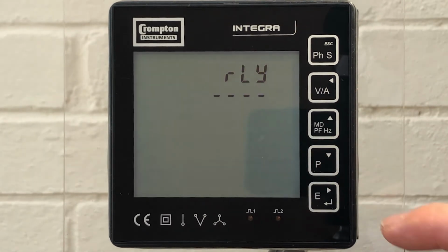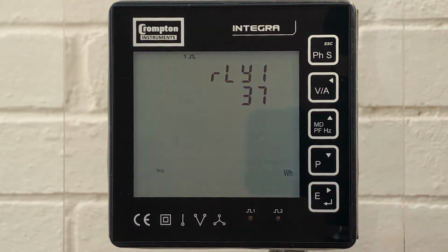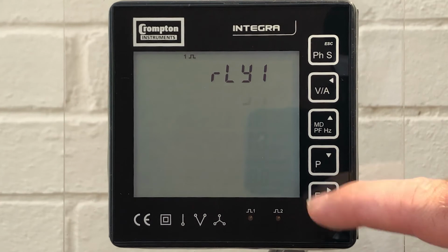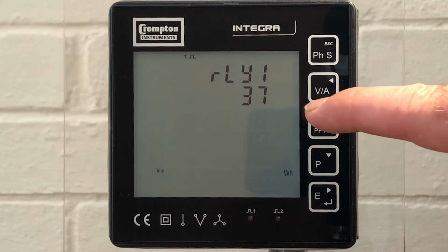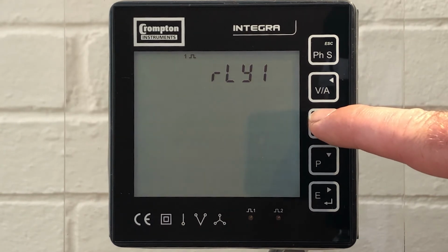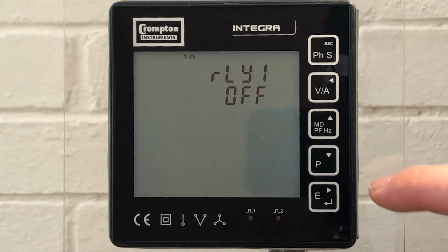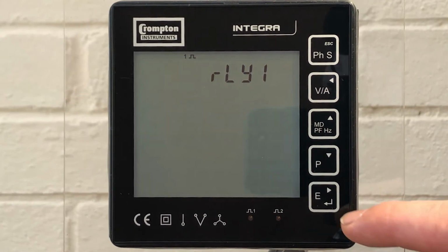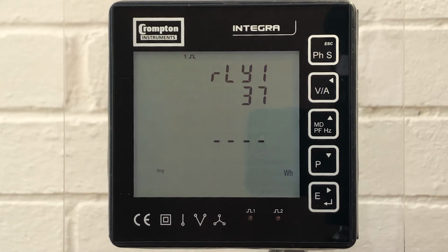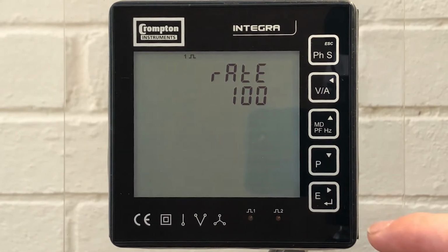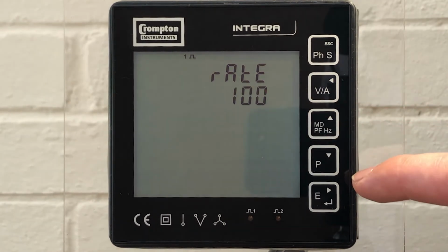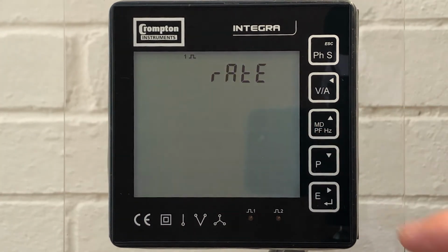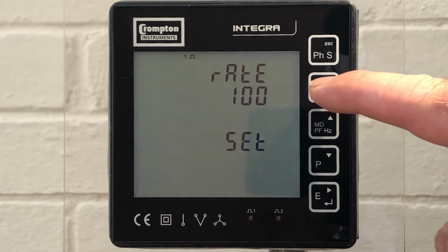And arrow down to our next settable feature, which is the relay output. The relay output can be set as off or to pulse on import watt hours, export watt hours, import var hours or export var hours. We'll set ours to import watt hours. If we press the VA button and arrow down to the next setting for pulse rate, we can select a pulse rate of 1 pulse per watt, 10 watts, 100 watts, 1000 watts, 10 kilowatt hours, 100 kilowatt hours or 1000 kilowatt hours. The reason we can't see all those options here is because the system set is a high power system, 132 kV and 1000 amps.